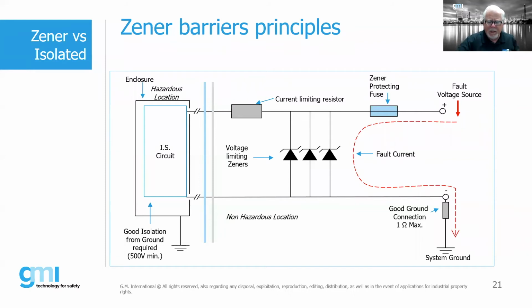all the protection concepts have to be able to withstand, have some sort of fault tolerance, if you will. And so for products that are suitable for zone 0 or an EPL-A, we actually have to have a double fault tolerant, if you will. So for a Zener barrier, we have to have redundancy in effect. If you looked at this little chart here, I can tell you that this is a schematic of an IA barrier, or a barrier that's suitable for protection into a zone 0, because we actually have redundancy built into it.